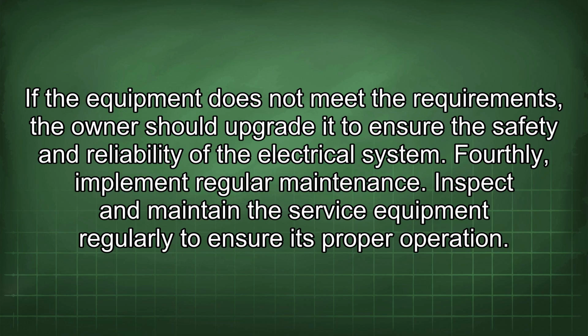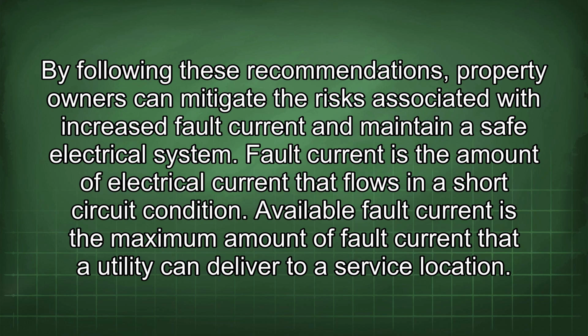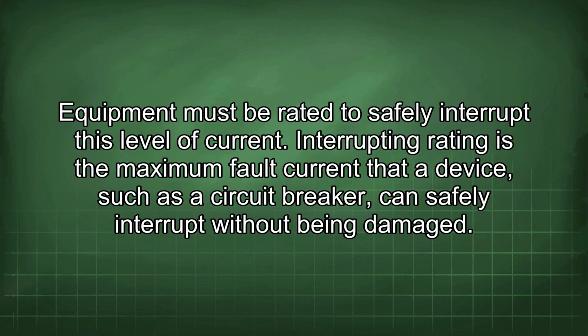Fourthly, implement regular maintenance. Inspect and maintain the service equipment regularly to ensure its proper operation. By following these recommendations, property owners can mitigate the risks associated with increased fault current and maintain a safe electrical system. Fault current is the amount of electrical current that flows in a short-circuit condition. Available fault current is the maximum amount of fault current that a utility can deliver to a service location. Equipment must be rated to safely interrupt this level of current.